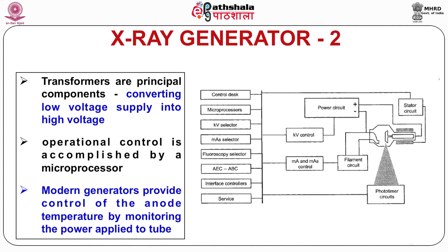X-ray generators have circuitry designed to protect X-ray tubes from potentially damaging overload conditions. Combinations of kVp, mA, and exposure time delivering excessive power to the anode are identified and such exposures are prohibited. Heat load monitors calculate the thermal loading of the anode based on kVp, mA, and exposure time, considering the duration for cooling. Some X-ray systems are equipped with sensors that measure the temperature of the anode and protect the tube and housing from excessive heat.